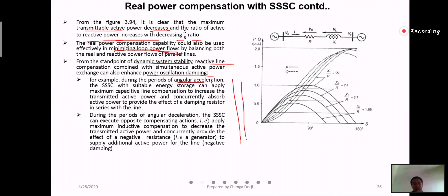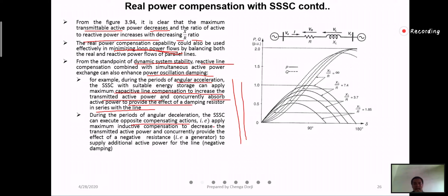During the period of angular acceleration — when the rotor is accelerating — the SSSC with suitable energy storage can apply maximum capacitive line compensation to increase the transmitted active power, and therefore absorb the active power to provide the effect of a damping resistor in series with the line. During deceleration, the SSSC can apply opposite compensating action — maximum inductive compensation — to decrease the transmitted active power and provide the effect of negative resistance, acting like a generator.